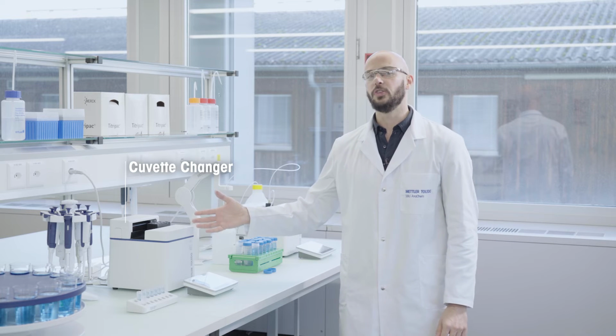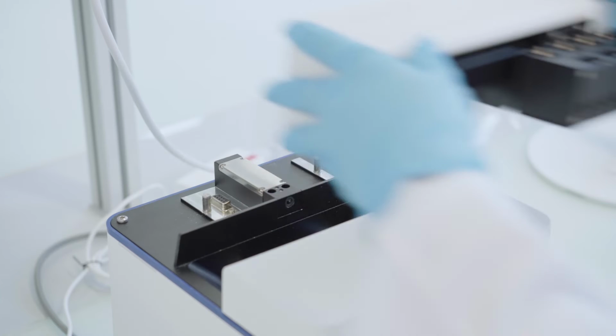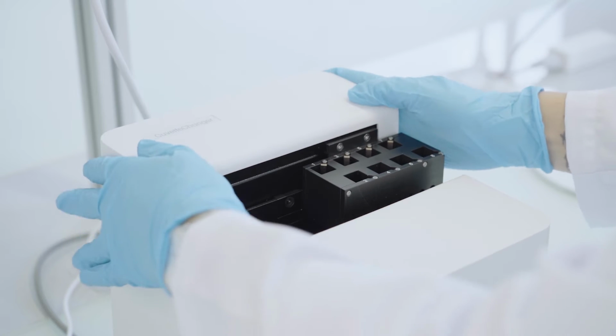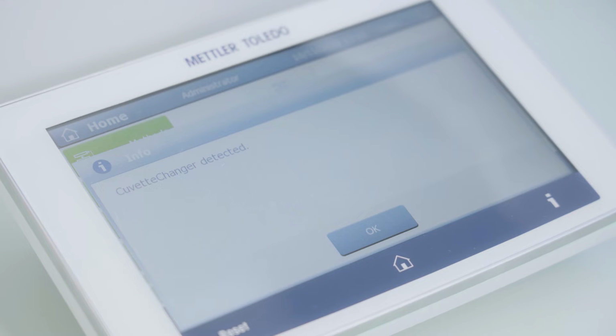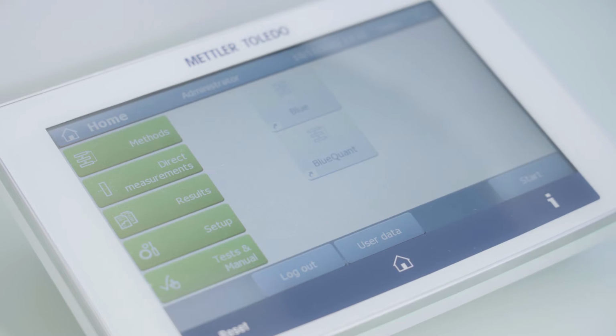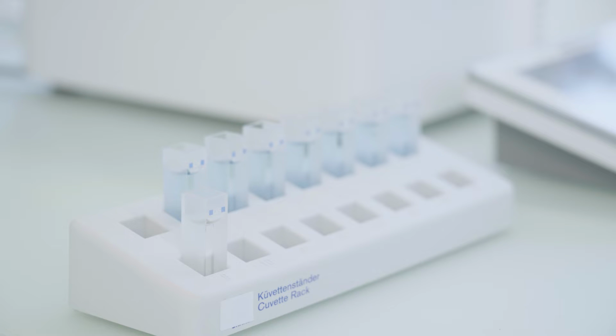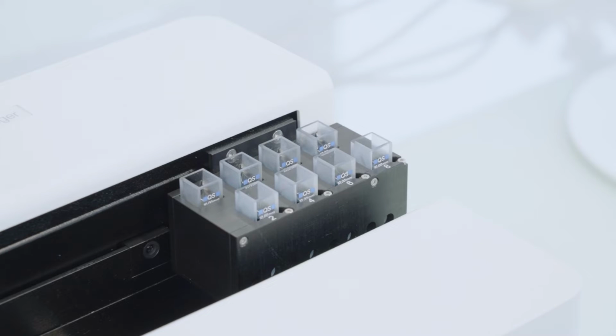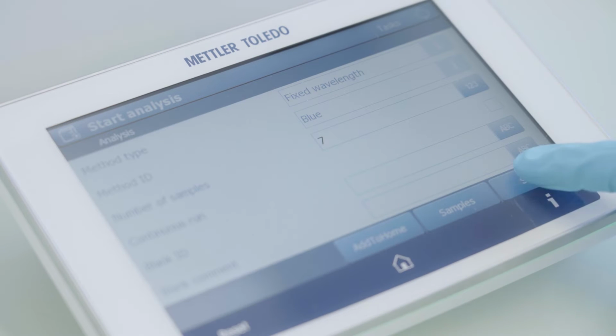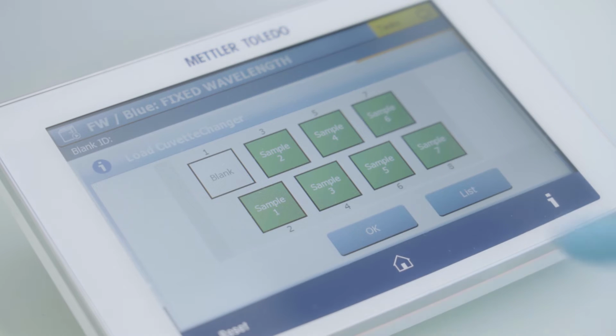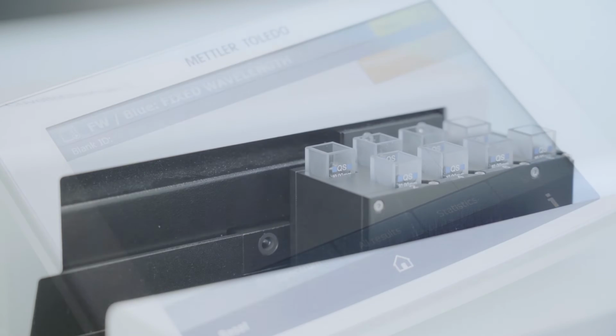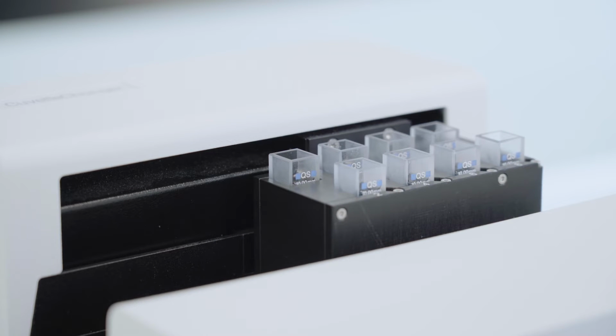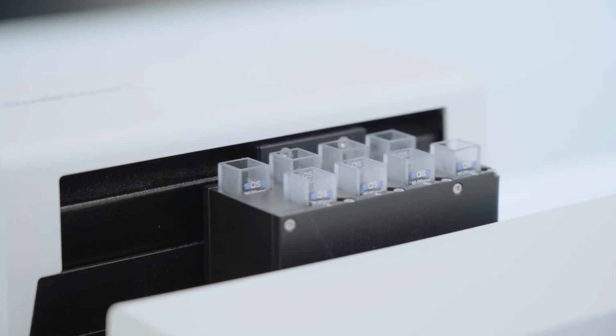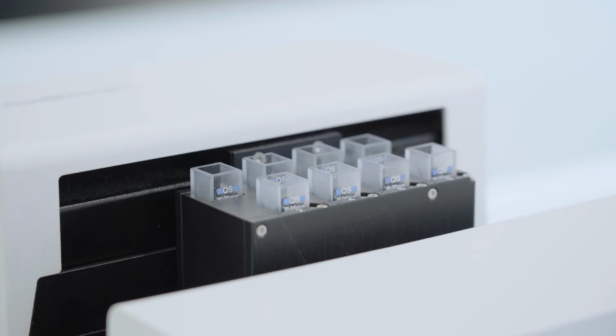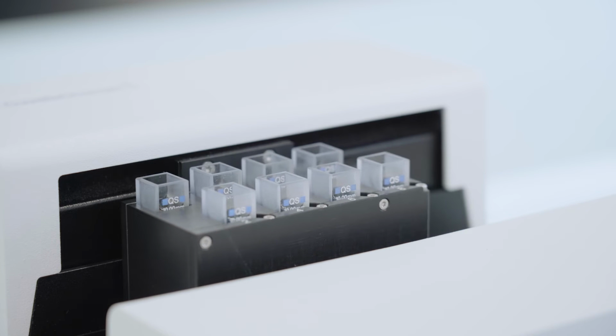For the automation of smaller sample series, the cuvette changer is the ideal solution. It can be mounted on top of the instrument, is plug and play and doesn't increase the footprint of the complete system. It can accommodate up to 8 10mm cuvettes simultaneously, and these can be measured in under 20 seconds. That makes it the ideal solution for quantification applications, as you can load your calibration standards and your samples in the changer at the same time and measure them in one run.